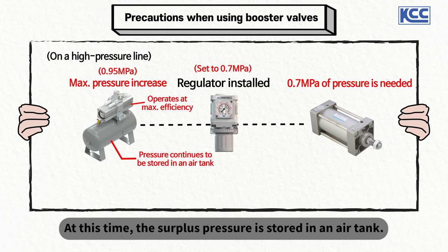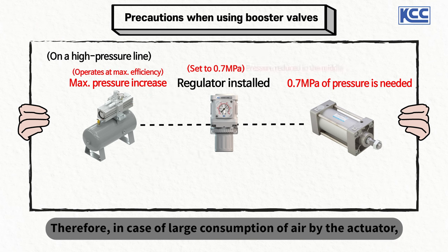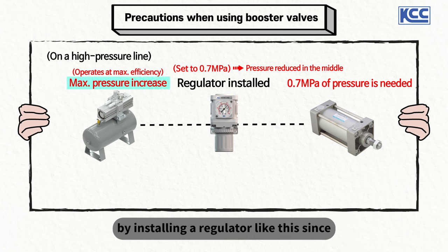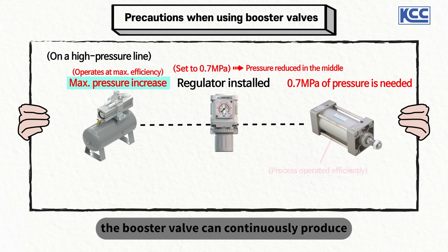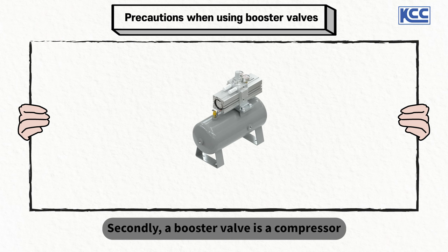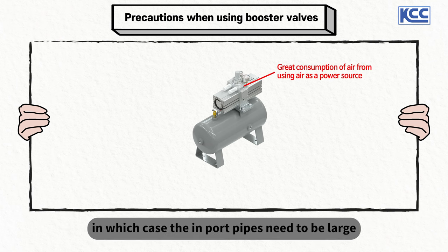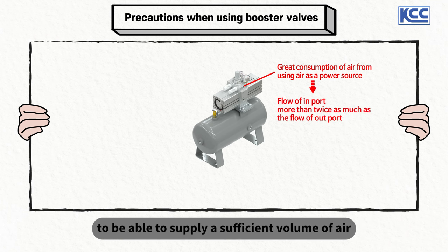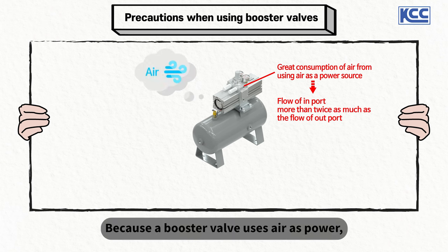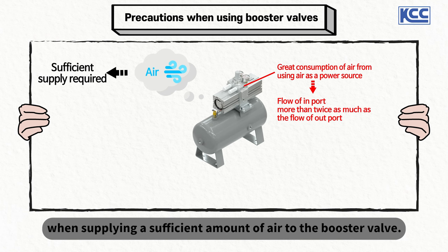At this time, the surplus pressure is stored in the air tank. Therefore, in case of large air consumption by the actuator, it is possible to run a process more efficiently since the booster valve can continuously produce compressed air to the maximum. Second, a booster valve is a compressor that uses air as its power, so it consumes a great amount of air. The in port pipes need to be large enough to supply a sufficient volume of air to the booster valve. Efficient use of the product can be ensured when supplying a sufficient amount of air to the booster valve.